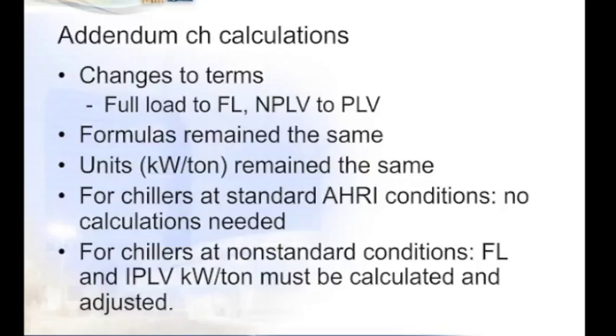Calculations have been part of 90.1 2010, and this addendum changed some of the terms, such as full load to FL and NPLV or non-standard to just part load value, particularly when it was calculated or recalculated as an adjusted value. Most of the formulas actually remain the same, and the units, kW per ton, also remain the same. So when you select a chiller to operate at AHRI standard conditions, you can just use the values from the table. No additional calculations are needed. You just select the chiller and meet the values or exceed them in most cases, and you're good to go. But for chillers selected at non-standard conditions, both the full load values and the IPLV kW per ton must be calculated and adjusted.